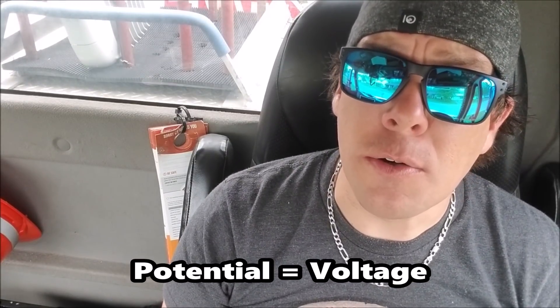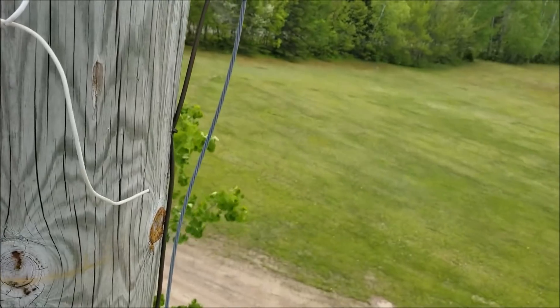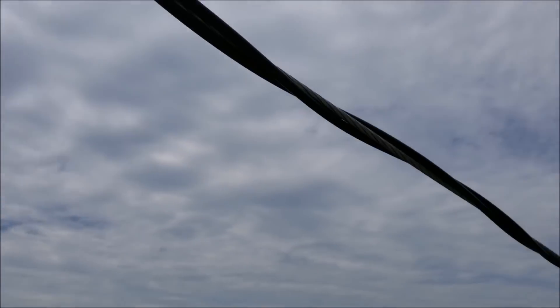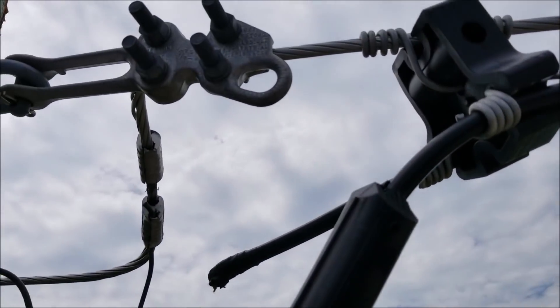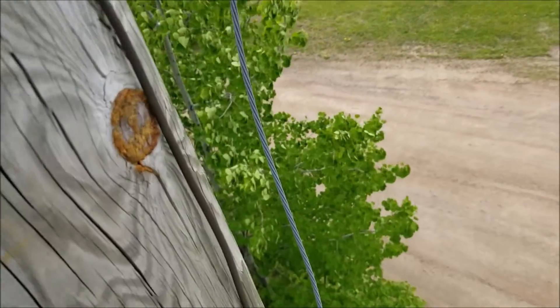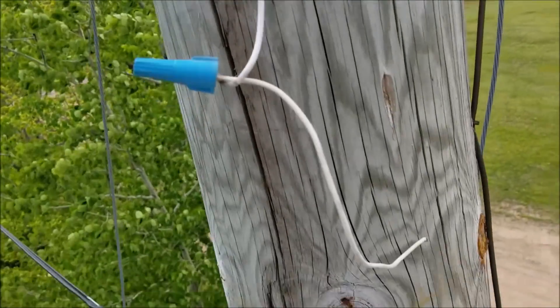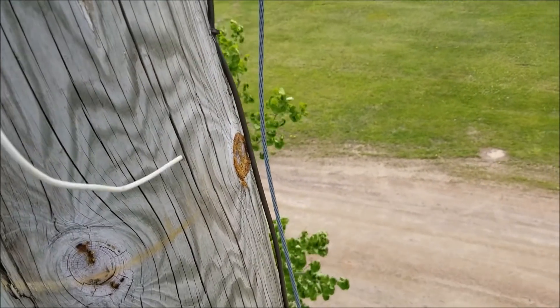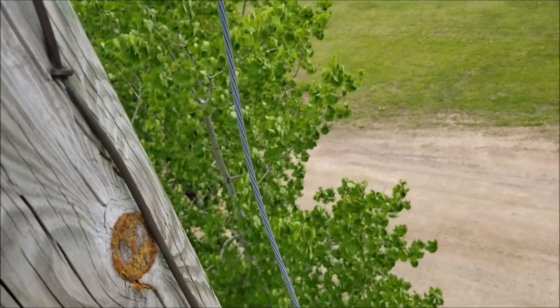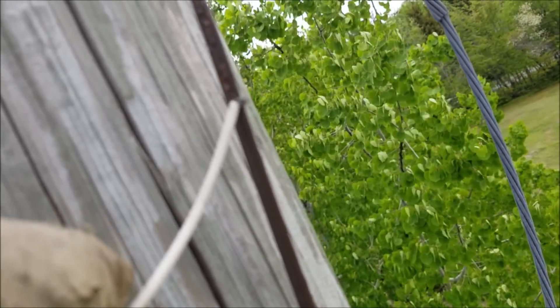It's just to show you how easily you can get a difference in potential between your neutral and ground wires. Take a look. The reason this light is out is actually the neutral wire being damaged. So you have your live wire going up to your triplex, your neutral wire which is grounded, your copper ground on the pole, and that copper ground goes to the ground. People steal these all the time. And here you have your neutral wire — this neutral wire which is grounded — and that's only feeding a 100 watt light bulb, nothing more.